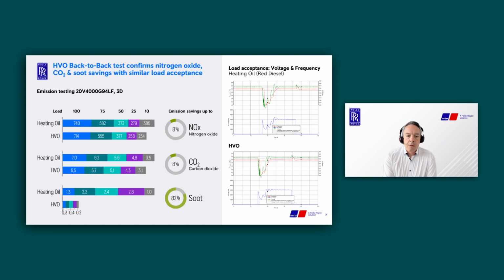On the right side, you see a comparison of something many customers asked us about: how is load acceptance, one of the key criteria especially for data centers, affected? As you can see, load acceptance is not affected at all. Any difference we measured during our back-to-back test was within the tolerances of our test equipment. By the way, we also did a load acceptance test on a KPP genset with the same outcome.